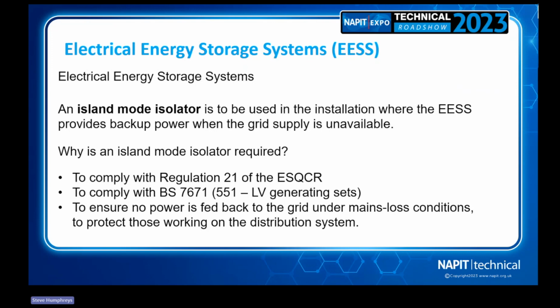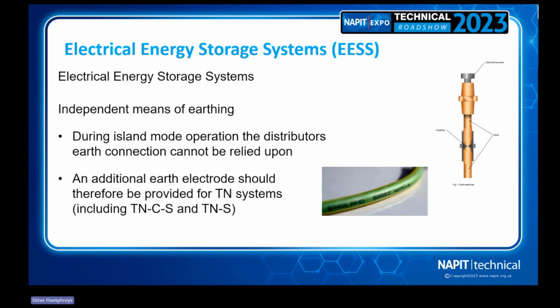So an island mode isolator causes a bit of grief in the industry as well, because is it internal to the actual inverter? Is it something that needs to be separately retrofitted external to the inverter? What we do know is that it needs to be something like a BS EN 60947-3. We can't really use contactors in this instance because a contactor can fail closed when it magnetizes, so we could be feeding back to the grid. So we've got to be careful and speak to the inverter manufacturers to check that it does what it says on the tin, which also lends itself to means of earthing.